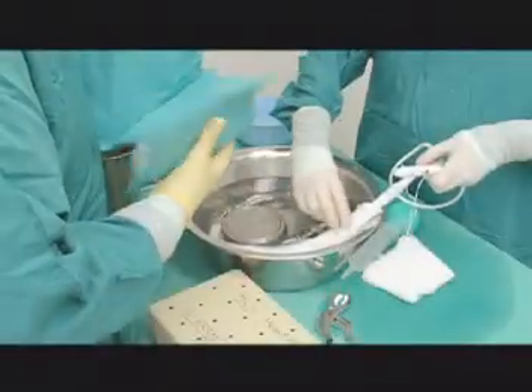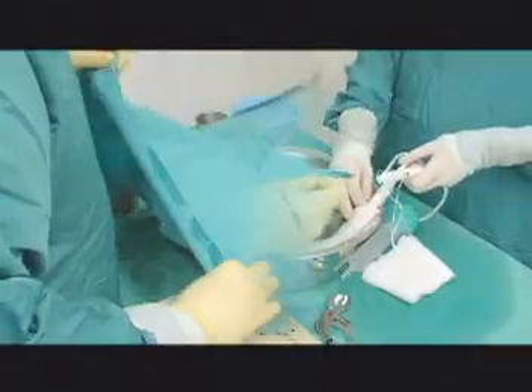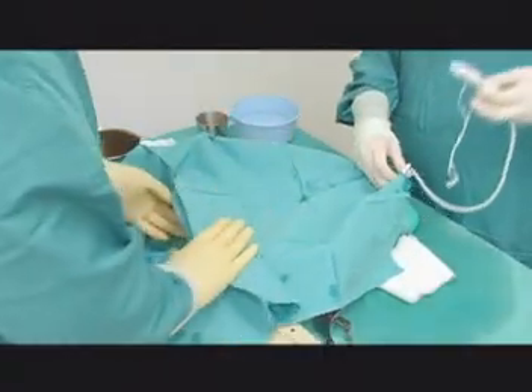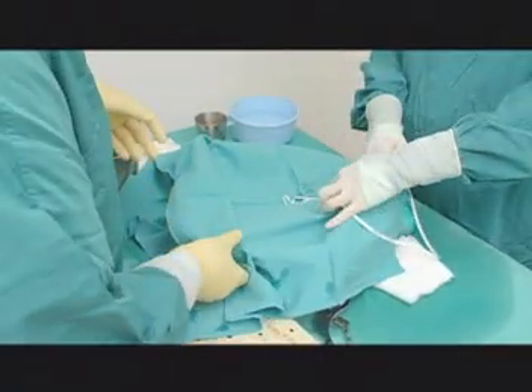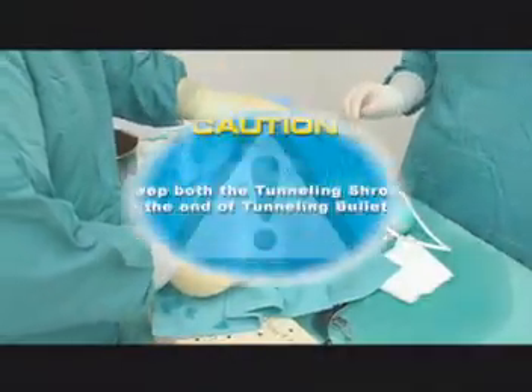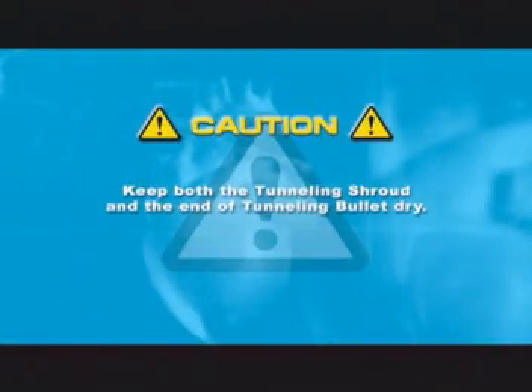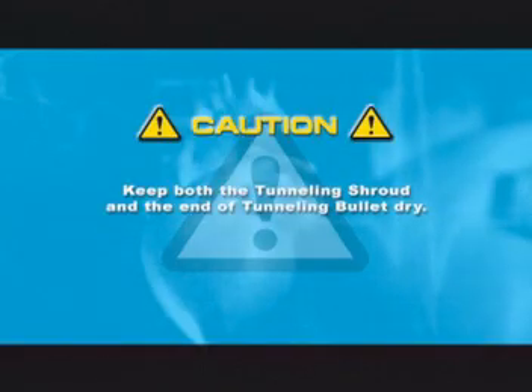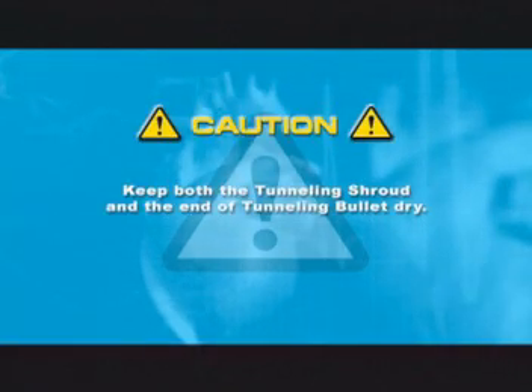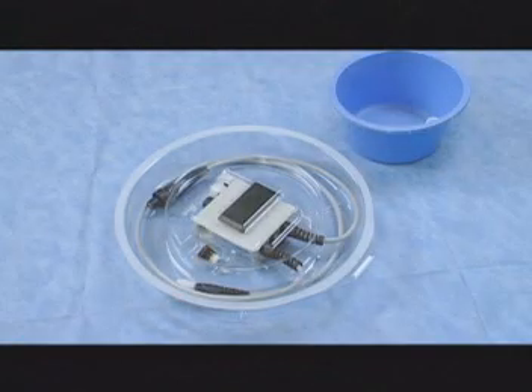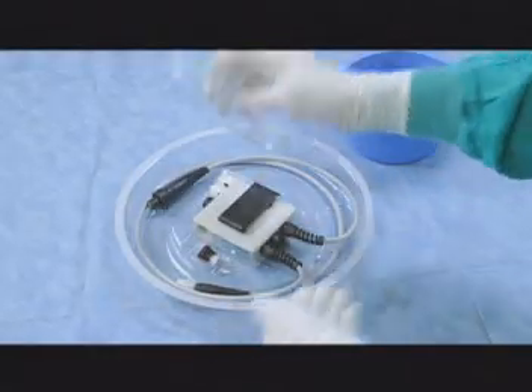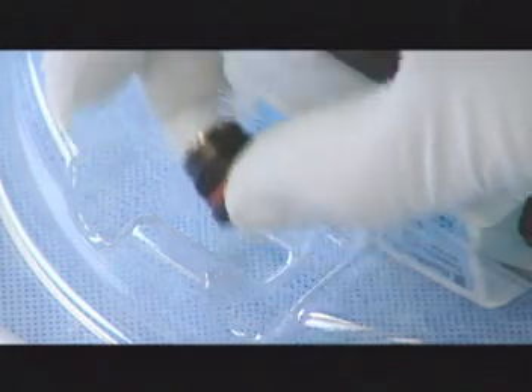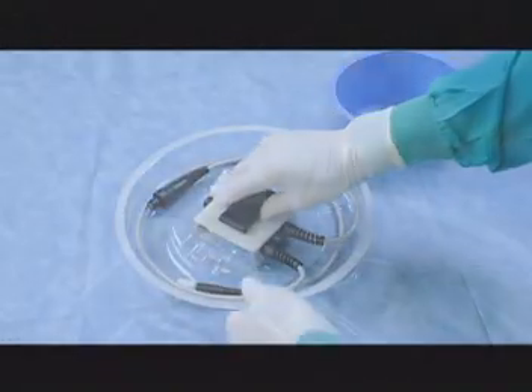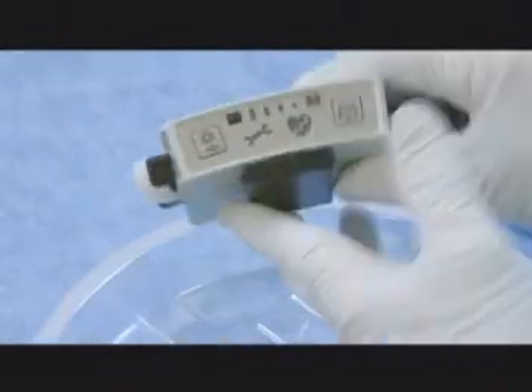Once primed, the LVAD pump may be left soaking in a covered basin containing an antibiotic bath until the surgical team is ready to implant it. Caution: keep both the tunneling shroud and the end of the tunneling bullet dry. After completing the pump assembly, remove the system controller and controller battery module from their sterile packaging. Place the sterile controller battery module in a safe location on the sterile field for use later.